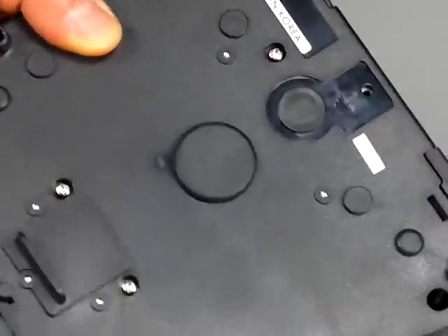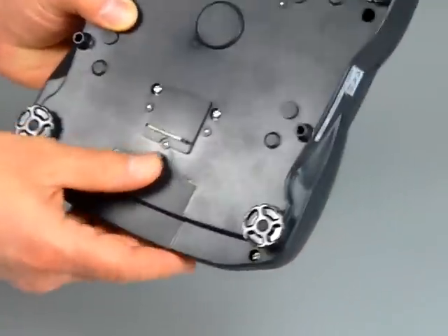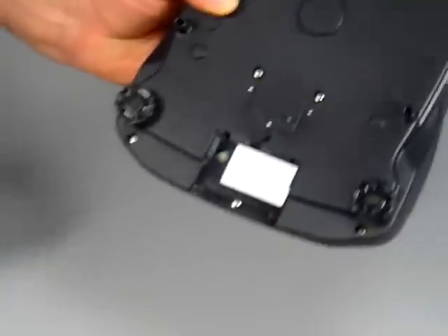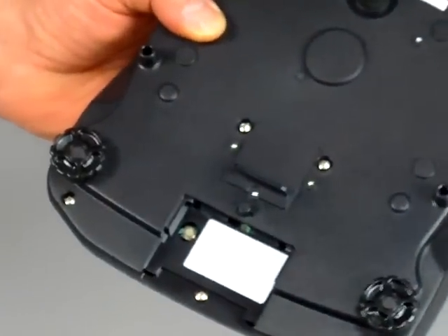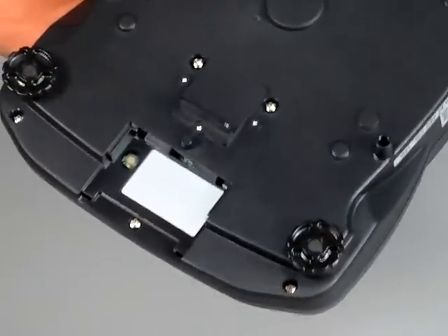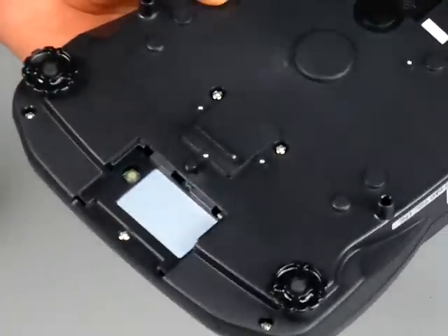We have four adjustable feet as I mentioned before. And this little compartment right here is so that you can do a calibration. There's a little button here, and our guess is eventually A&D will apply for legal-for-trade status — this is why they have this compartment, so it can be locked out. But presently, this model is not legal for trade.